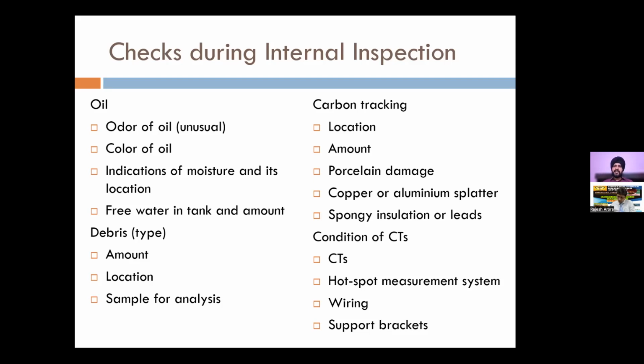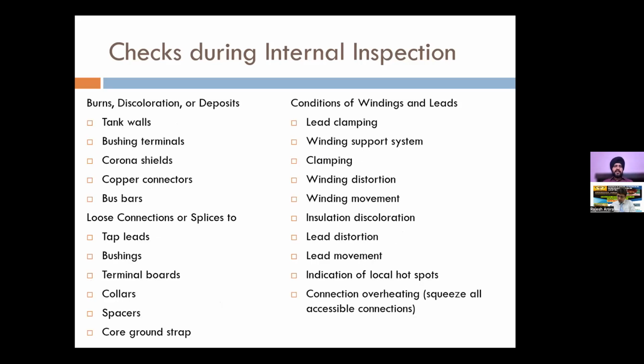So it is very critical that you note down each and every starting point, ending point, so that you can hypothesize later on what is the nature of the failure. Then condition of the CTs, if there is any issues, many times CTs, some carbon spot or over voltages, transients that they occur, they can also be seen. So the condition of CTs also need to be taken into account. Then burns, discoloration and deposits on the tank wall, bushing terminal, corona shield, like I just said.